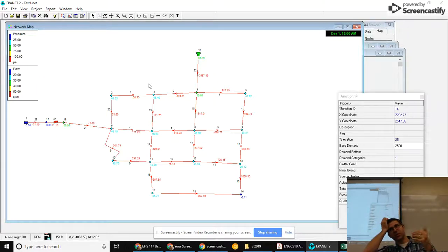But a lot of systems will allow the system to temporarily be down to, say, 20 psi if there's a fire somewhere. So while the fire's going on, we're at 20, and that's okay. So our system met spec under the normal condition. It was 57 psi. That's good. Now we've got a fire, and we're not good.